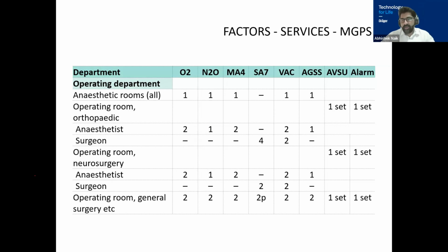So AGSS, nowadays there is a concept which is getting famous, which is called green anesthesia. They don't want any harmful gases present in the anesthesia room or the operating room, because the people who work in the OT work there for almost 10 to 12 hours of a day, and breathing these gases can have a long-term effect on their body and health. So to prevent that, these gases have to be removed, and this is where the anesthesia gas scavenging system works in a very efficient way.